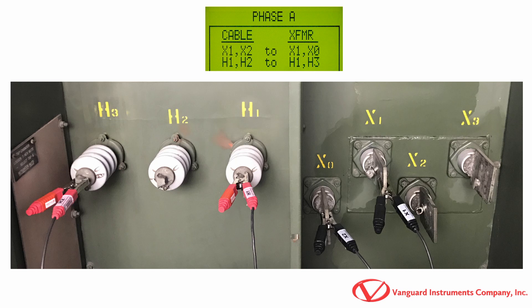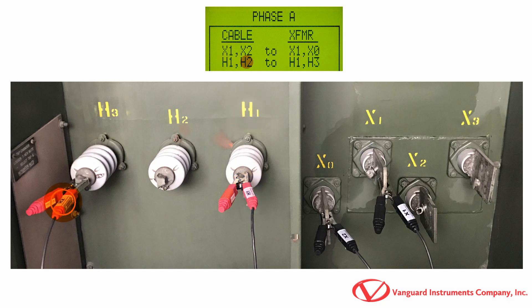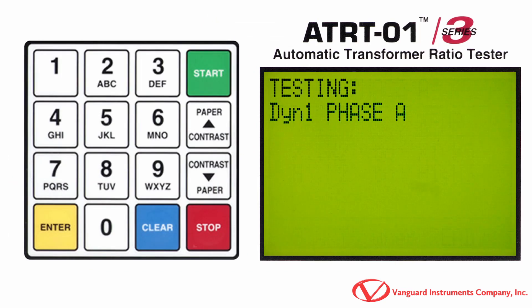For our example, we'll connect the unit's X1 cable to the transformer's X1 terminal and the unit's X2 cable to the transformer's X0 terminal. Next, we'll connect the unit's H1 cable to the transformer's H1 terminal and the unit's H2 cable to the transformer's H3 terminal. Now press the Start key to perform the test.